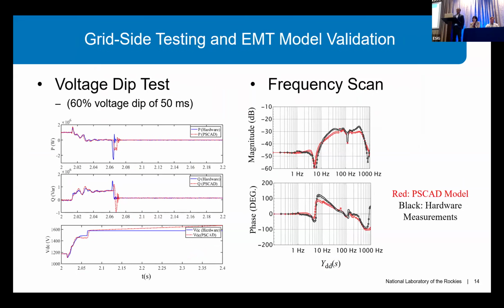Of course, we can also do the traditional tests like low voltage ride-through and impedance scans to test compliance with various voltage ride-through standards, as well as use it for testing the model quality, validation of the model. So on the left, you see a test we ran on, I think, a 2.x MVA PV inverter for a voltage dip test, where we reduce the POI or the interconnection voltage by 60% for 50 milliseconds. And the response here compares the actual measurements with the PSCAD model. So it not only serves as testing the compliance with the ride-through performance, but also for model validation.